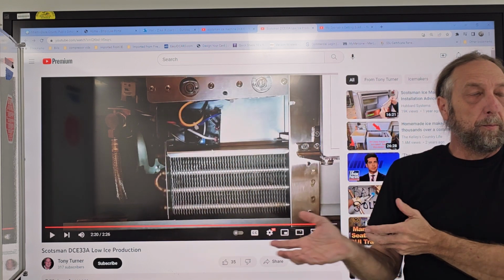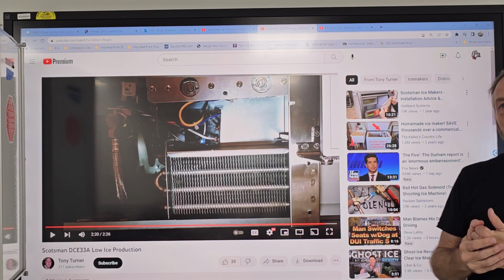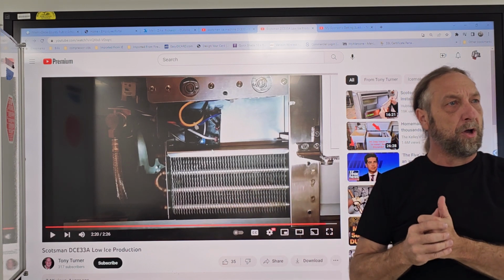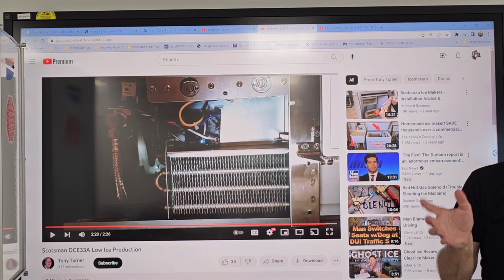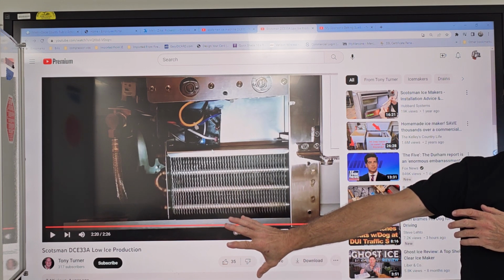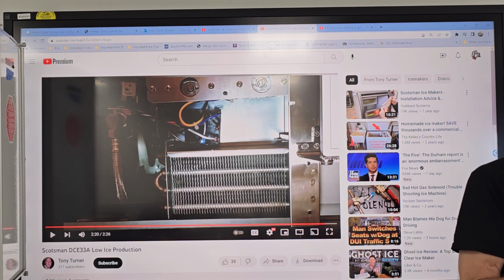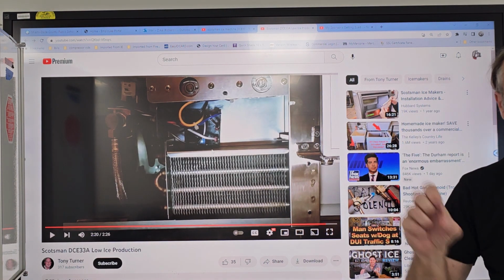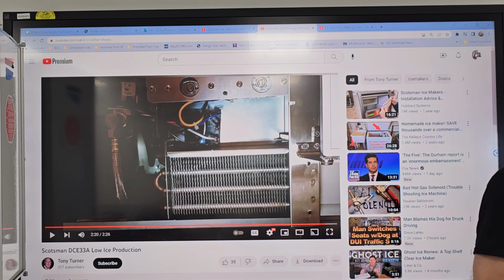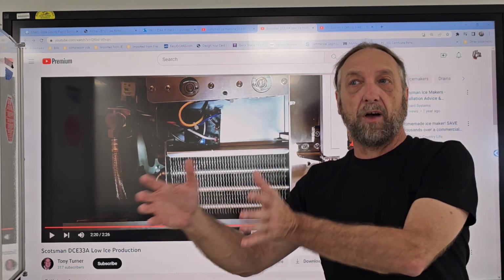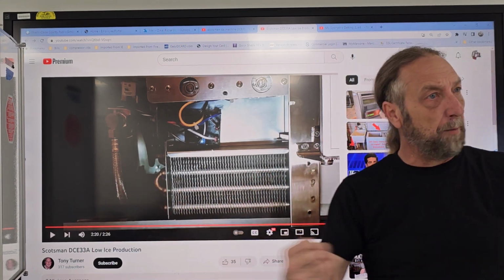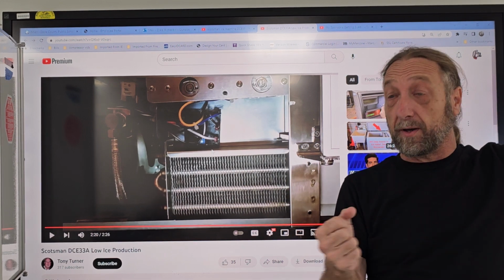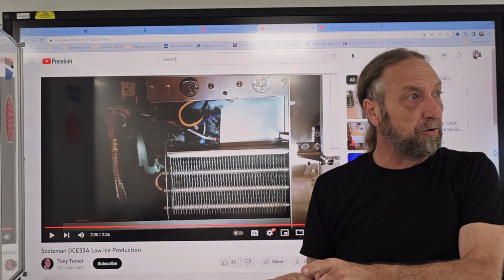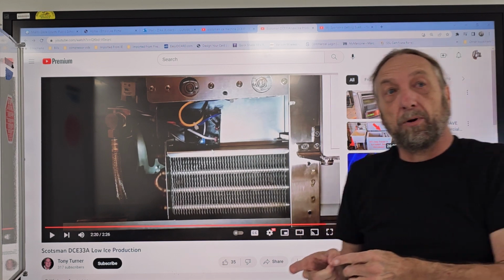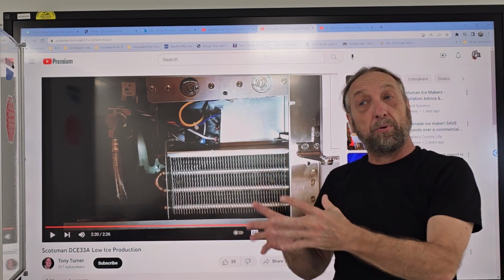Okay? So normally on a refrigeration system with 134A, we run about a 0 PSI evaporator. We run about 120 to 130 high side pressure, condenser pressure. But with the coils being dirty, we're going to raise that head pressure, which is a term we use on the high side. Okay? If you raise the head pressure, you're putting more stress on the compressor because it's trying to pump into the condenser, but now I've raised the pressure of the condenser, I put a strain on the compressor. And by not releasing the heat properly, what happens then is compressors are like car engines.